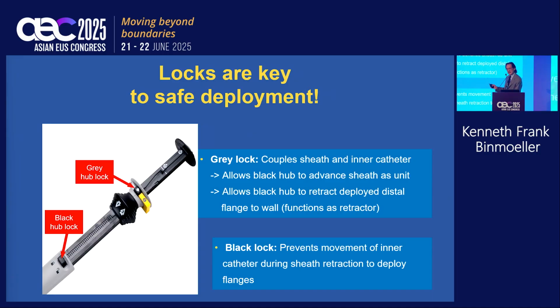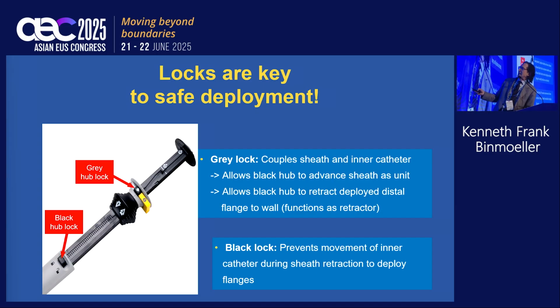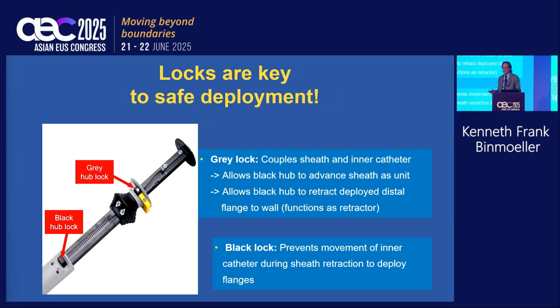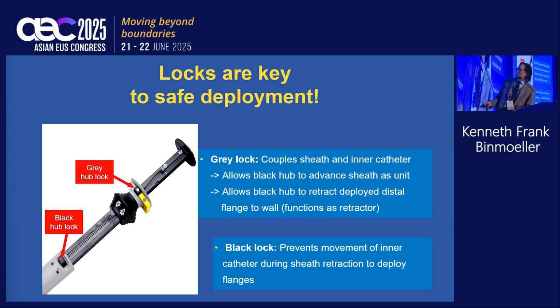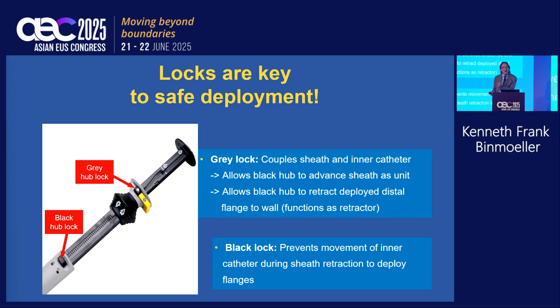The locks are key to safe deployment. You're always locking and unlocking in sequence. So you have to always remember that. After you do one action, you need to lock. Do the next action, lock. So the gray lock is what couples the sheath and the inner catheter, so it allows the black hub to advance the sheath as a unit. And it allows the black hub to retract the deployed distal flange to the wall. It really functions like a retractor. The black lock prevents movement of the inner catheter during sheath retraction to deploy the flanges. It's important that you immobilize that inner catheter while you're retracting your sheath to deploy the flanges.